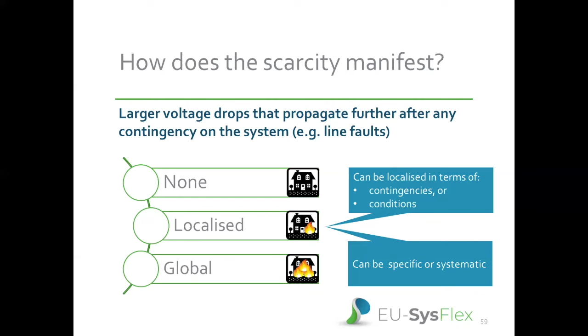Now how does the scarcity of dynamic voltage control manifest from our perspective? I think the key thing is you have larger voltage drops that propagate further across the system. This can be a localized scarcity or a global scarcity - that's about the number of contingencies that generate this problematic voltage drop, or the spread of the voltage drop itself. One thing to bear in mind is that if you have a lot of localized problems, you have to start thinking of it as a global problem, or you're going to find suboptimal solutions - a patchwork quilt of local answers to what really was a global problem.